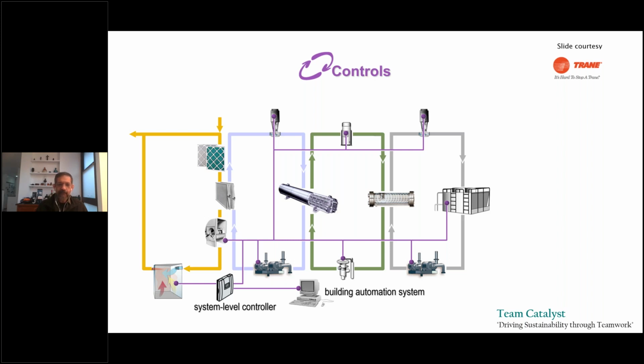What's a control strategy? Well, when you don't need the full capacity, you may be able to slow down the fan. You may be able to have not so cold supply air. You may be able to slow down the amount of chilled water you're pumping. You may be able to slow the compressor for the chiller. You might be able to slow down the cooling tower fan, or you might be able to slow down the amount of the condenser water. There's many options possible. That's what the problem is.